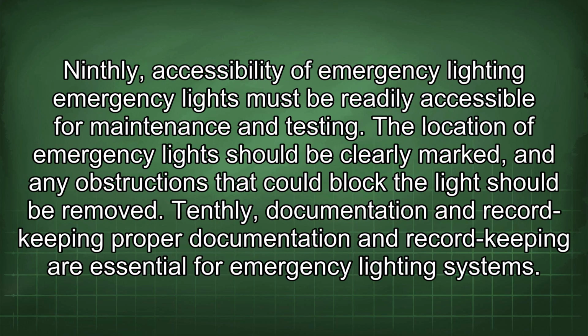Ninthly, accessibility of emergency lighting. Emergency lights must be readily accessible for maintenance and testing. The location of emergency lights should be clearly marked, and any obstructions that could block the light should be removed.